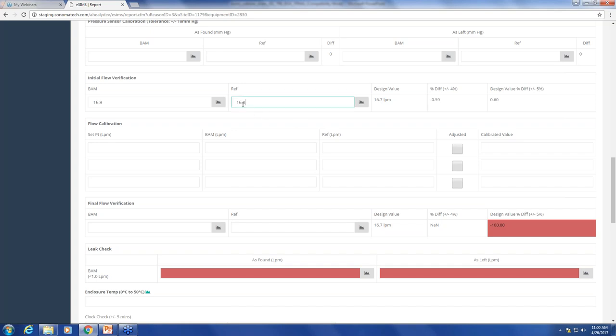But just for kicks, let's pretend our reference is reading 18 liters per minute and our BAM is reading 15 liters per minute -- we're just way out of spec. We can see right off the bat we have indicators that we need to take action here. We'd actually need to do our flow calibration after all, and then go ahead and do another flow verification check after that.